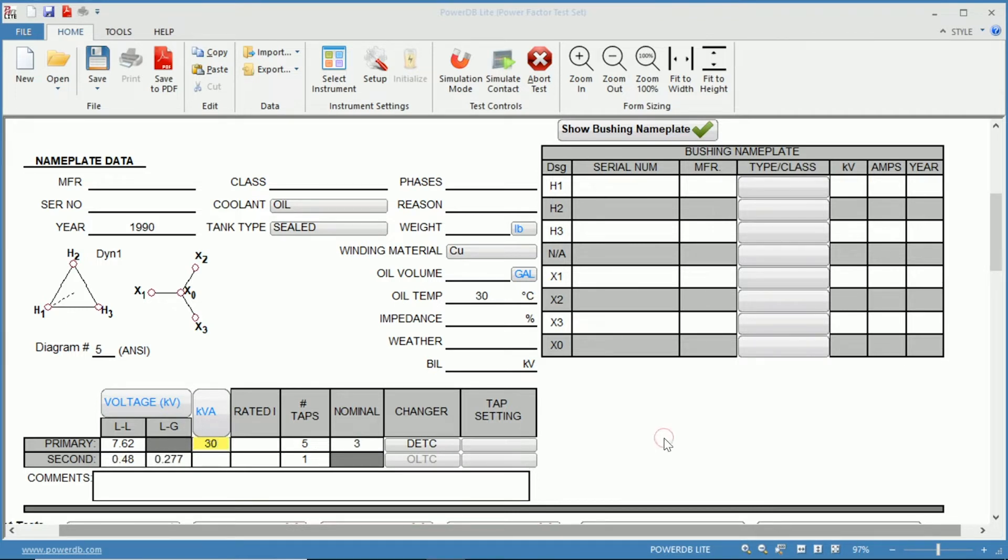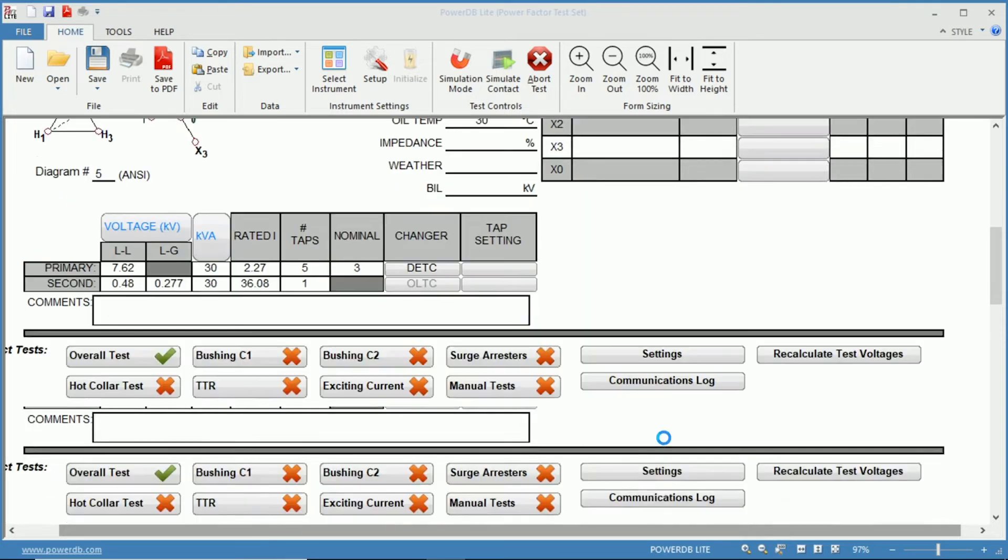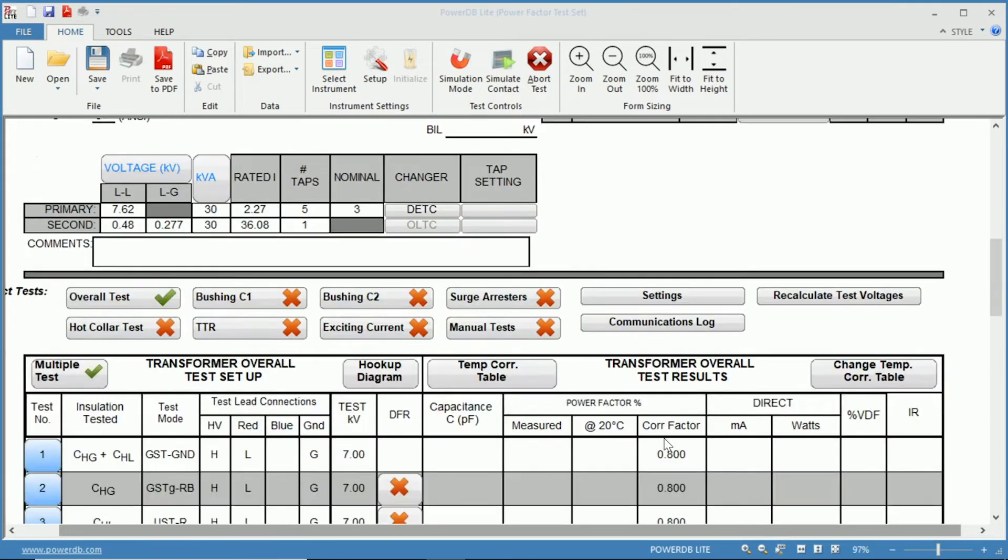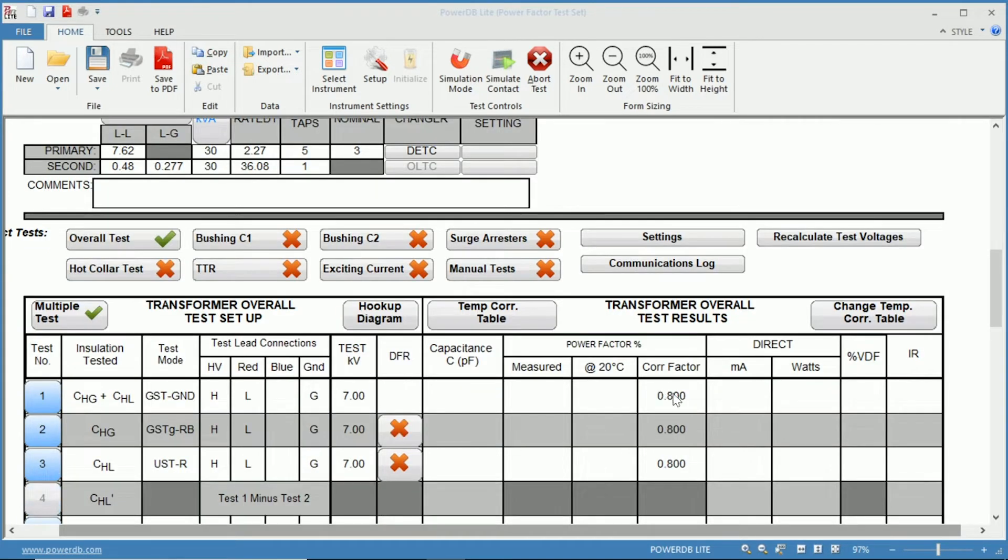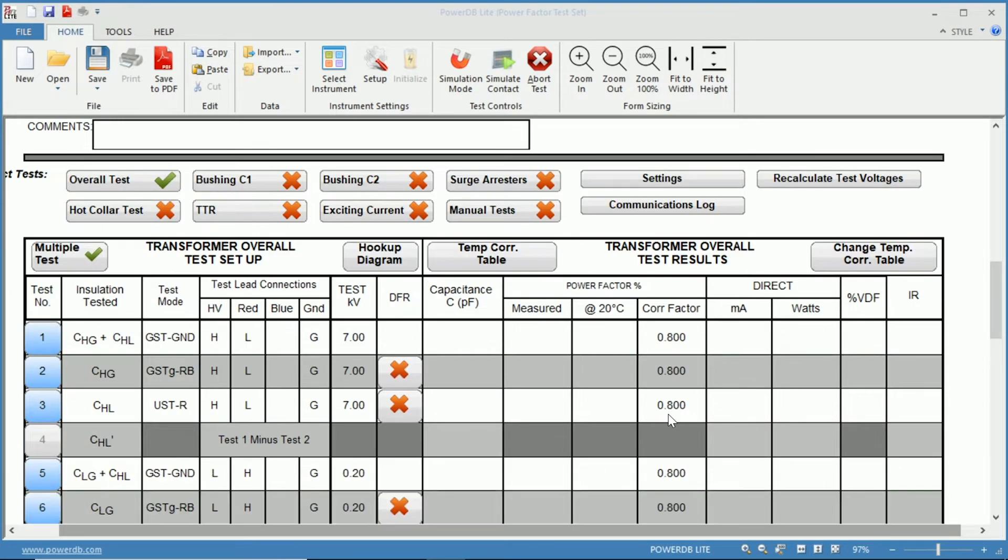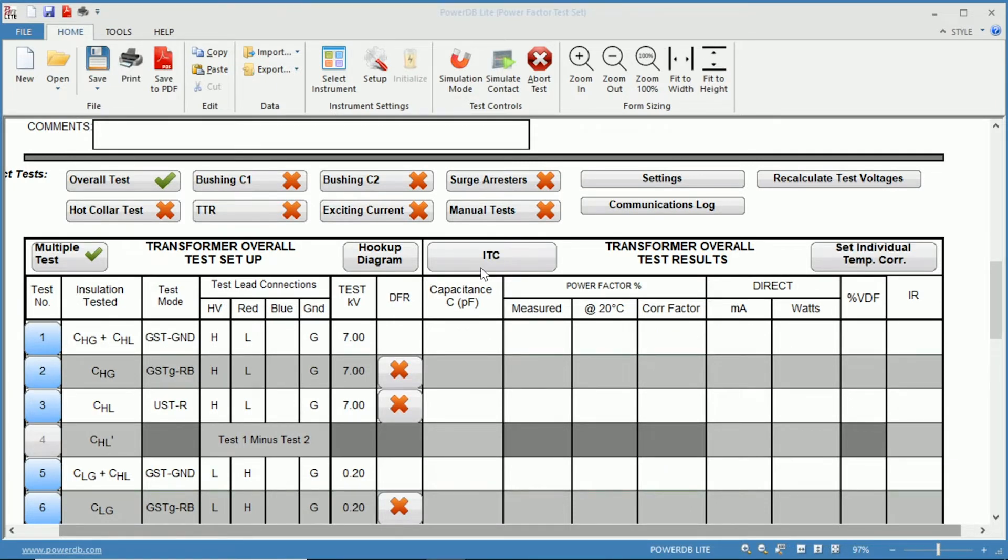And now we have our rated current. So now if we were to use the temperature correction tables we can see we have our correction factor. Now there is another option if we click here to use ITC which is the individual temperature correction, and this is a correction factor that is created for the transformer that you're testing.